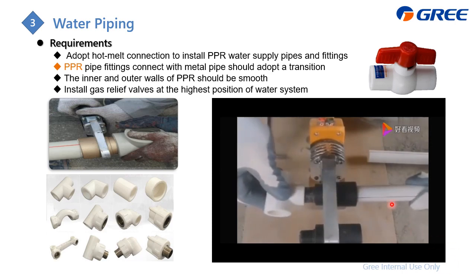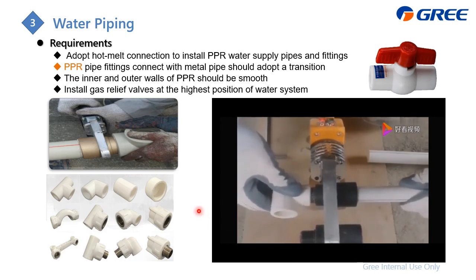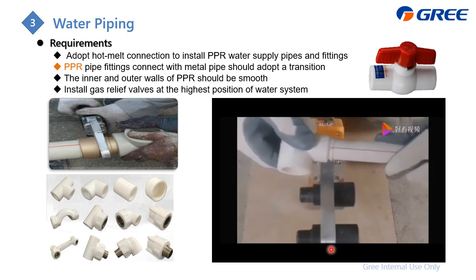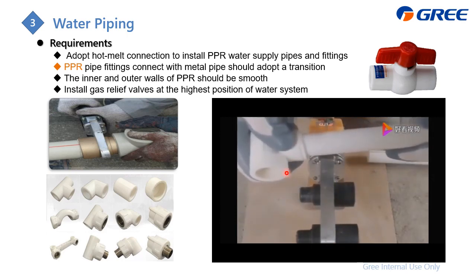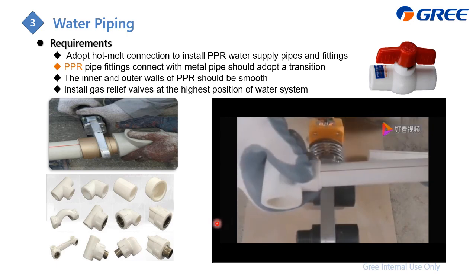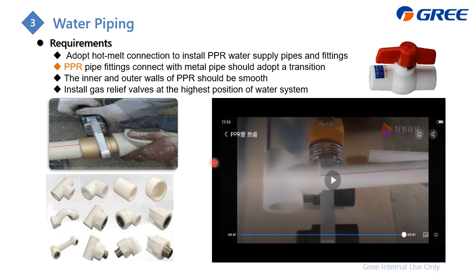And for this one, this time we're going to connect this pipe with this three-way. After melting for enough time, we can put it together and also just ensure there is no gap. And this is finished. Also, for the PPR pipe, the inner and outer walls should be smooth. And also, you need to install a gas release valve just to release the air trapped inside the water system at the highest position.